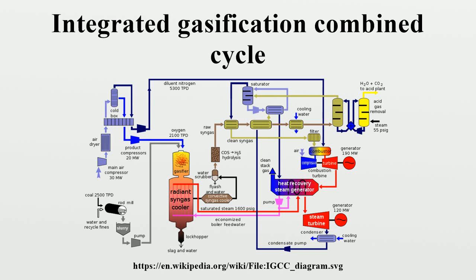There are several advantages and disadvantages when compared to conventional post-combustion carbon capture and various variations, and these are fully discussed at reference 6. Cost and reliability. The main problem for IGCC is its high capital cost, upwards of $3,593 per kW. Official U.S. government figures give more optimistic estimates of $1,491 per kW installed capacity v. $1,290 for a conventional clean coal facility, but in light of current applications, these cost estimates have been demonstrated to be incorrect.